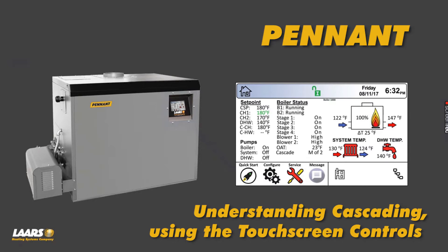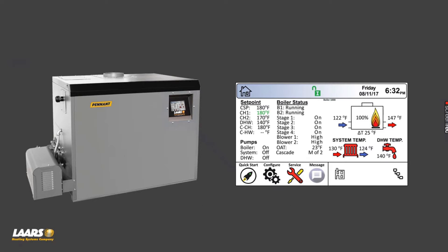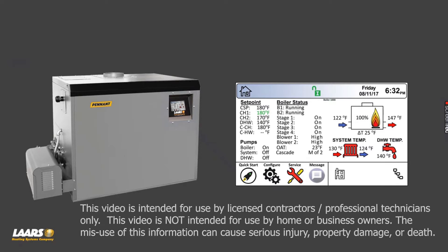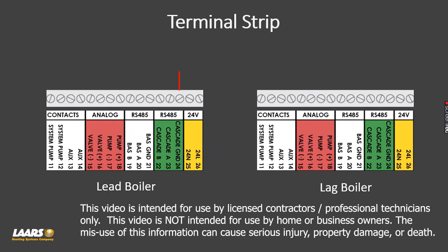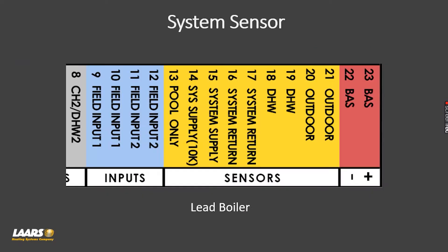Understanding cascading of the Laars Pennant controls — we can cascade up to eight Pennant boilers. First, confirm that the wiring from your lead to lag boilers has been completed. Next, also confirm that your system sensor has been installed on your lead boiler only.